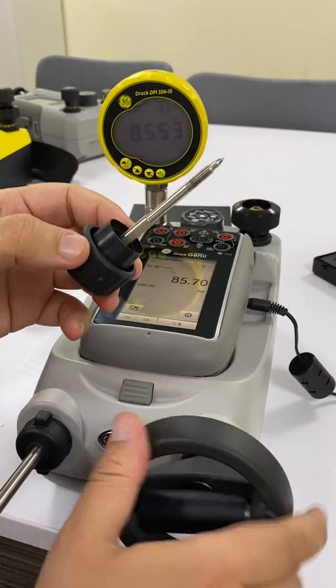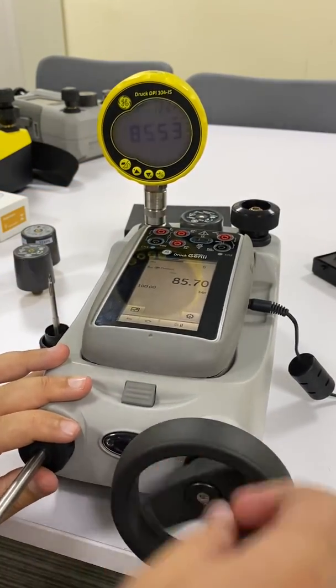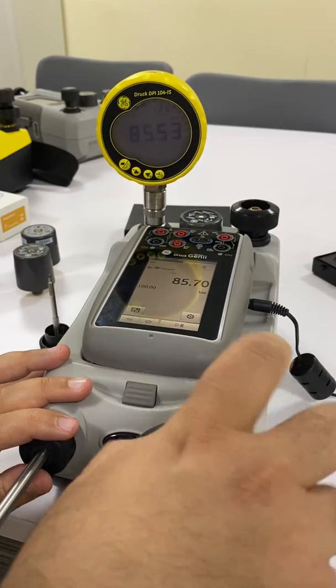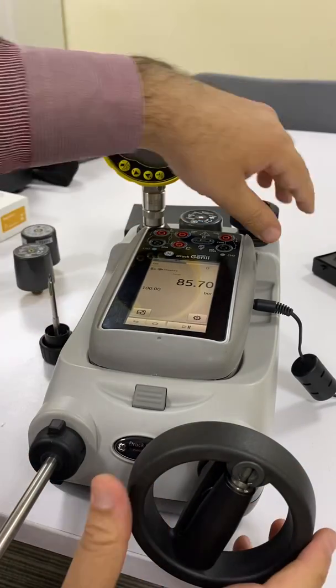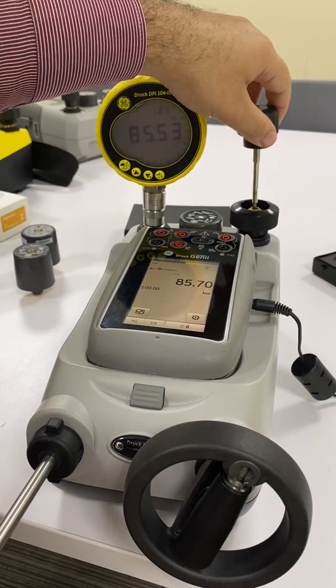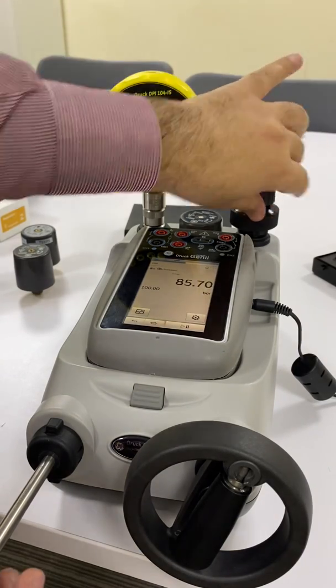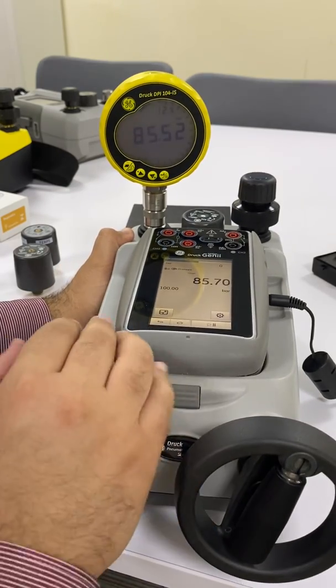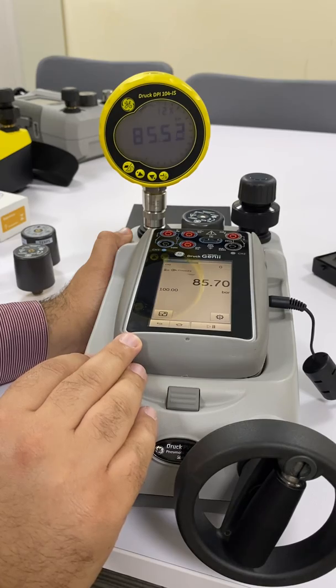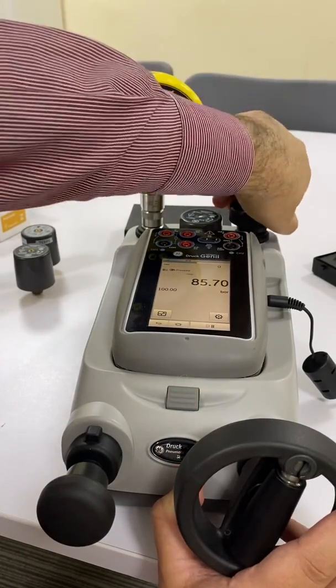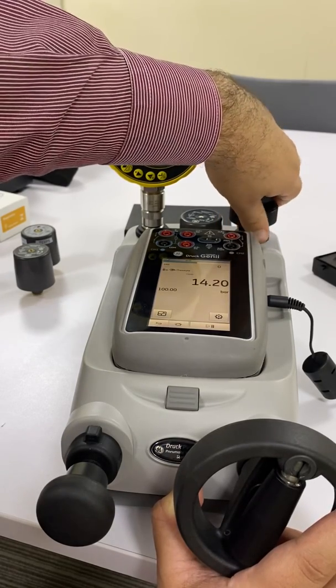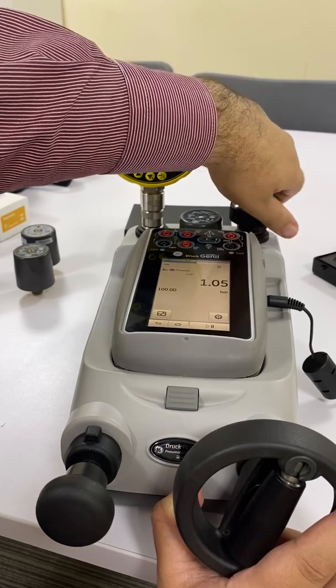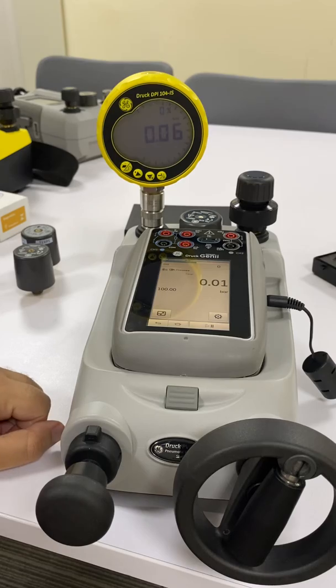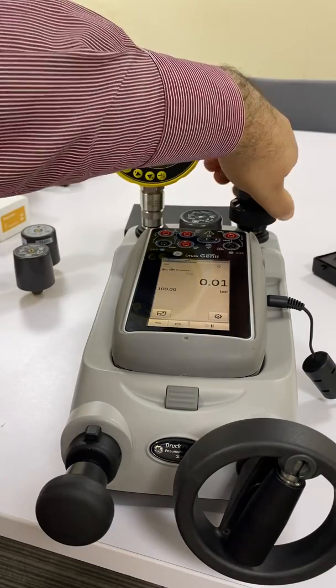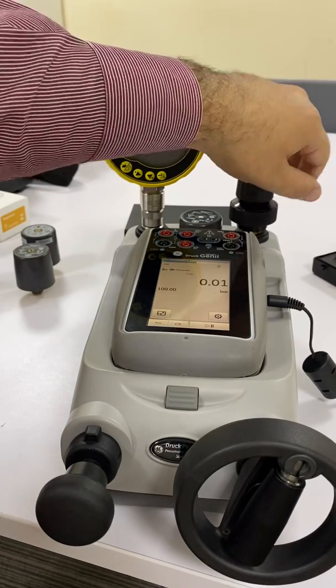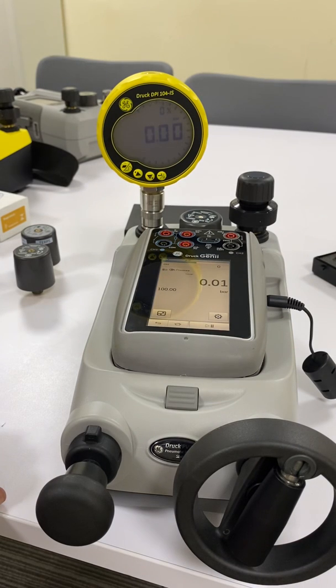So I'm now taking this fully. The pressure is still holding at 85, which means that I am having a pressure hold inside the instrument. Let me return this now and try something with you. I'll now use this. See, it's fully free, so I can start from zero and build more pressure. If I open the bottom valve, I will return the chamber to the zero. As you can see, the pressure releasing is so safe, it's gradual, and I can do the proper control on the calibration.